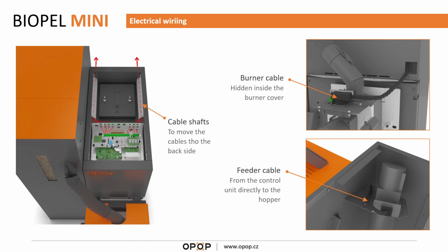Okay, and then of course when you buy the boiler you have to decide on which side the pellet hopper will stand. So in this case, in this picture, you see that the pellet hopper is on the left side, so you connect the cable for the feeder through here. So you can see cable connected here to the feeder, which goes through the side of the pellet hopper to the control unit. And then of course you connect also the cable of the burner here. So there is opening space here, and the cable itself is basically hidden behind the cover of the burner and behind the front cover of the boiler, and again goes up and it's connected to the control unit.